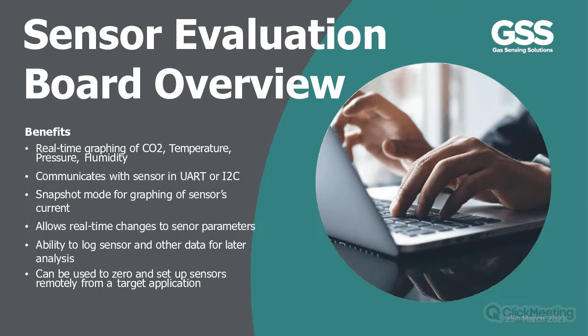It gives you the ability to control it from the PC, gives you some real-time graphing of CO2 recorded from the sensor, and also, in addition to that, from the board itself, we can get temperature, pressure, humidity, etc. It allows you to speak to a variety of our sensors depending on which interface module you've got, and it does that in either UART, which is standard for most of our sensors, or I2C, where it's appropriate. This allows you to make real-time changes to the setup of the sensor, and it has the ability to log data, which you can import into Excel or other options to view.